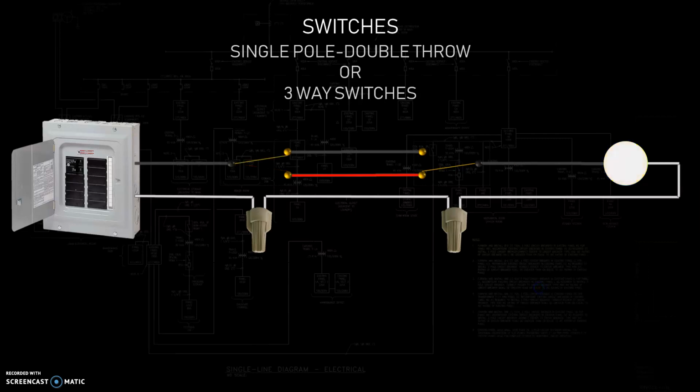Right? And let's complete the cycle here, and we flip this switch and our light is now off once again. So again, no matter which combination, which switch you throw, your light should always change. If that's not the case, the most common mistake is you have one of your traveler wires landed on your common screw. That's 99.9% of the time when there's a mistake in three-way wiring. That's it.